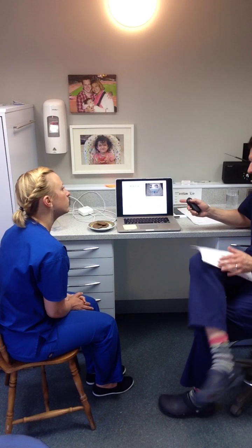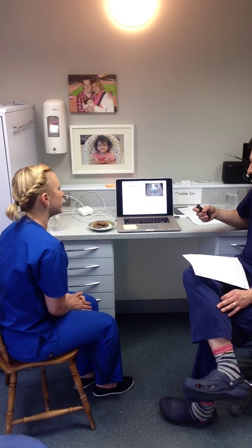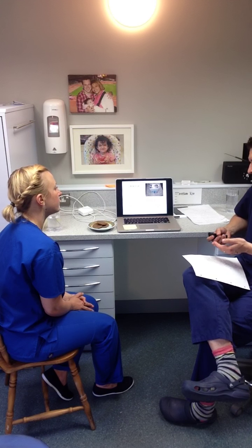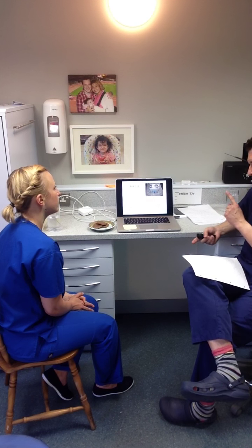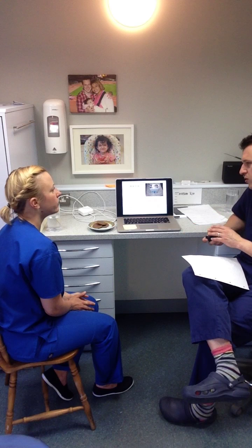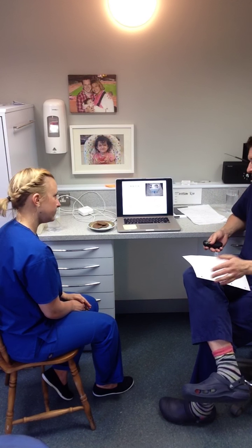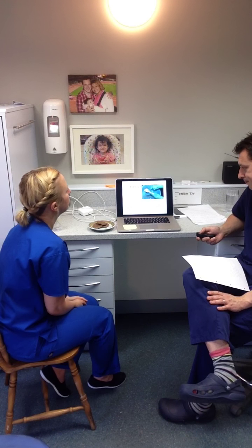The problem with ultrasonic bath cleaning is that it can take a good few minutes to clean, and if you've got material stuck on there and you've not physically had a scrub beforehand, it may not come off. So you might have to swap the manual cleaning with the ultrasonic cleaning, or it might be good to do the manual cleaning first, then rinse it, and then put it in the ultrasonic bath to agitate it. Yeah, that would probably be the best way to do it.